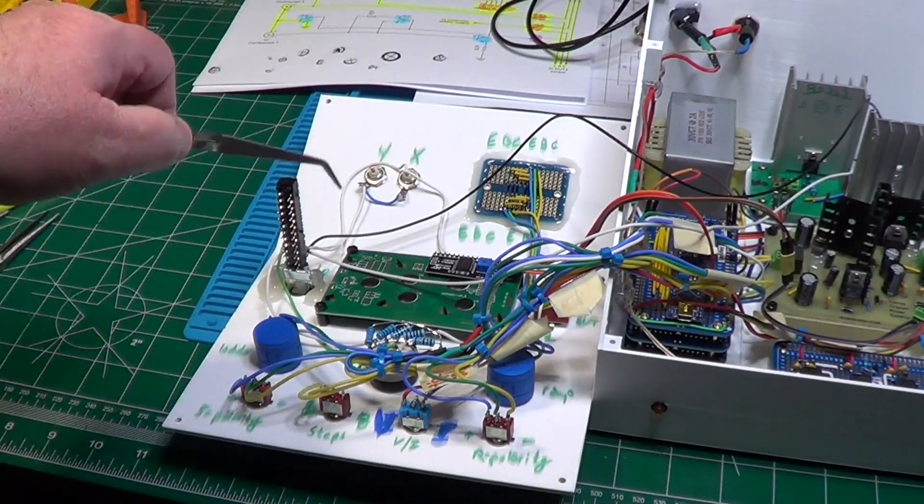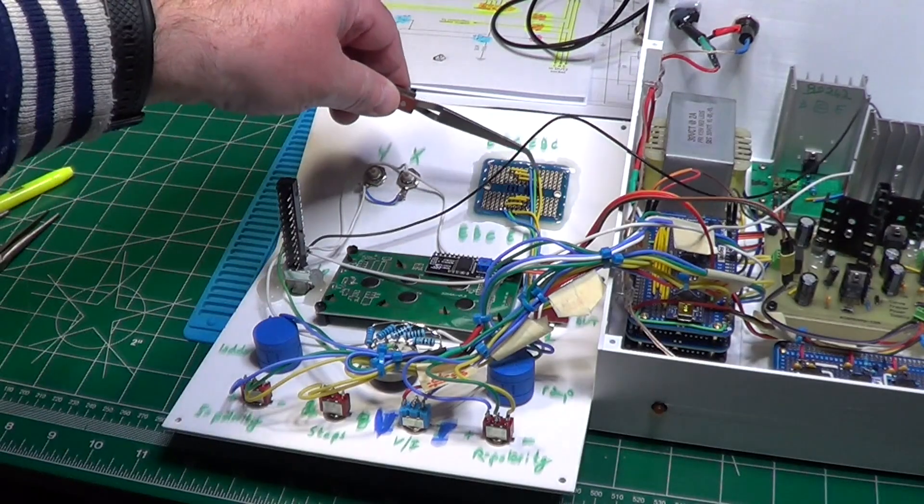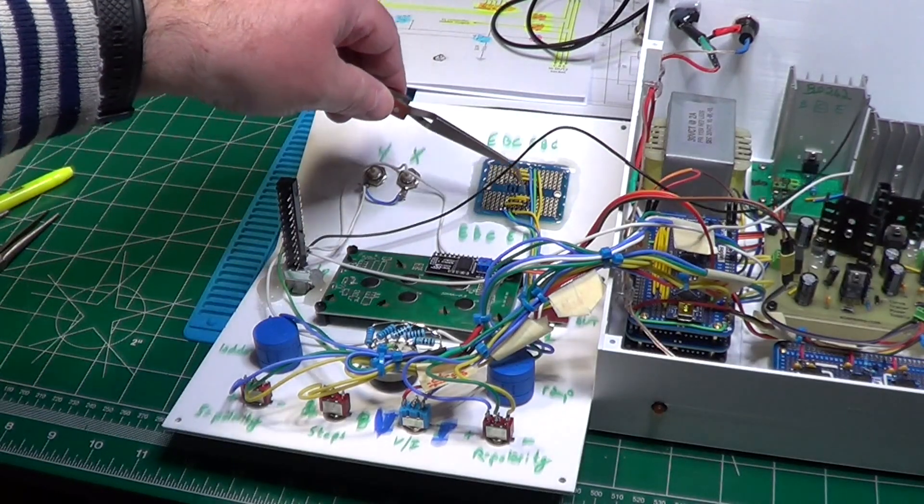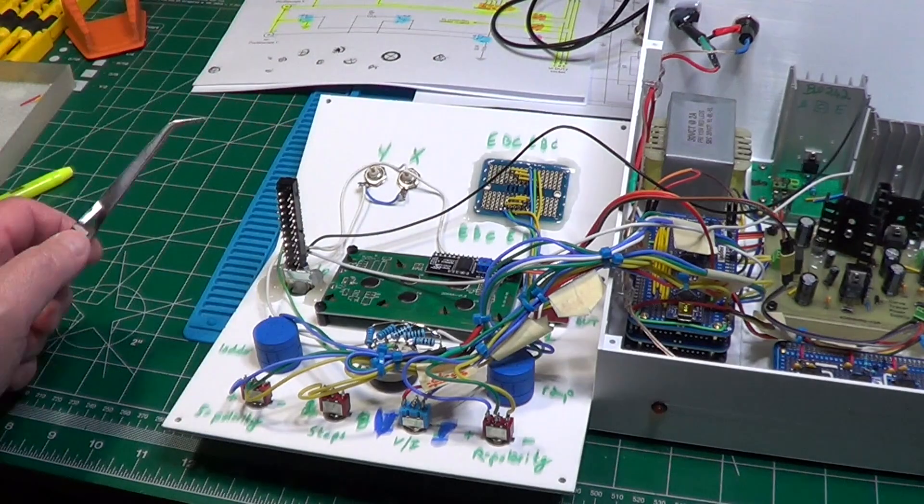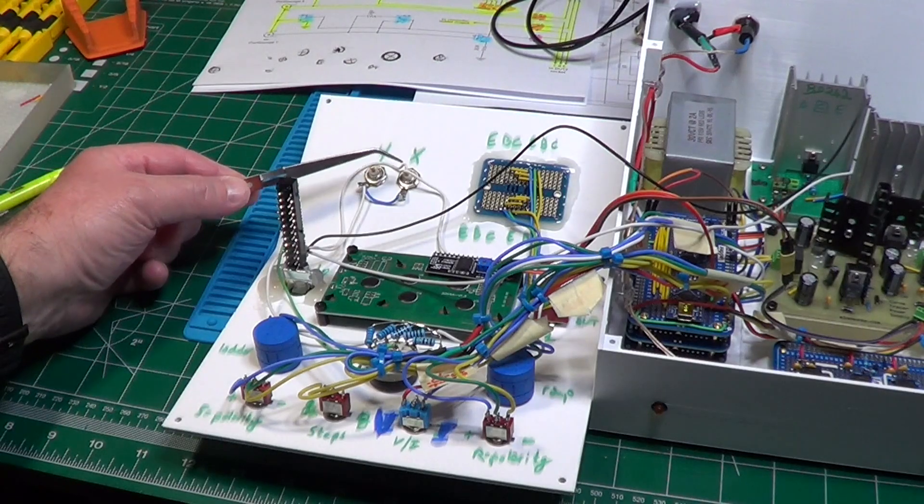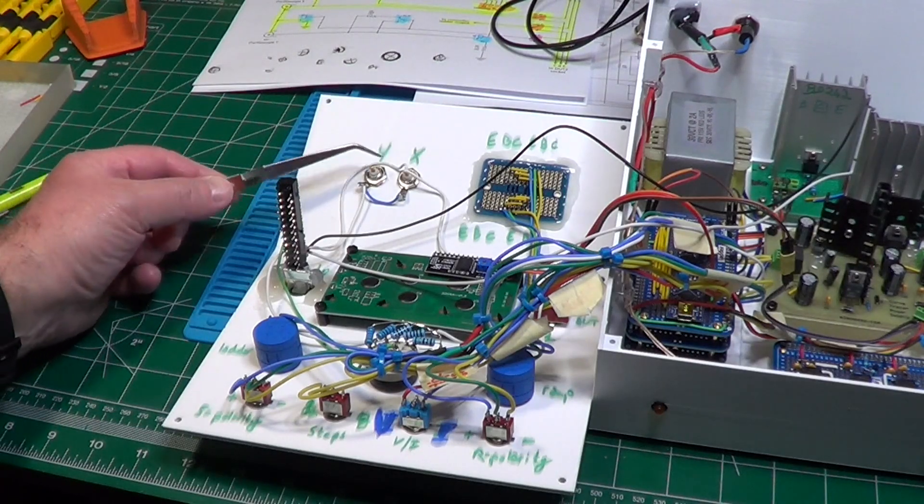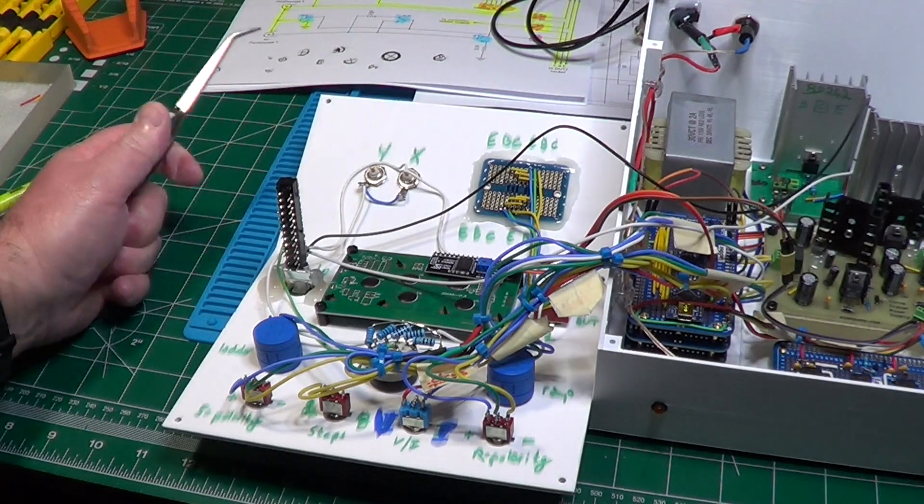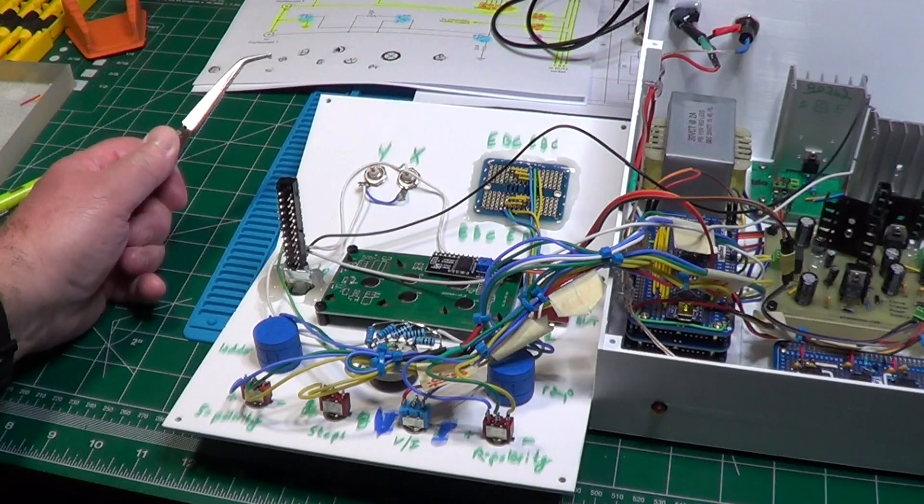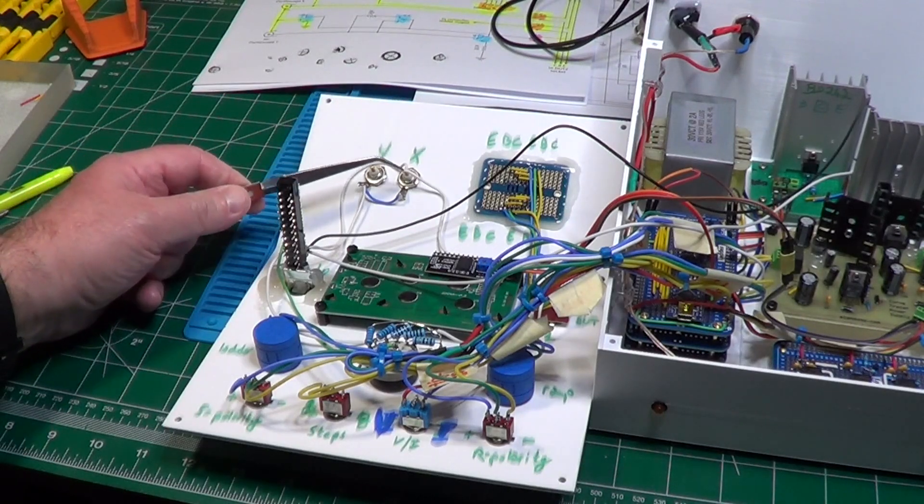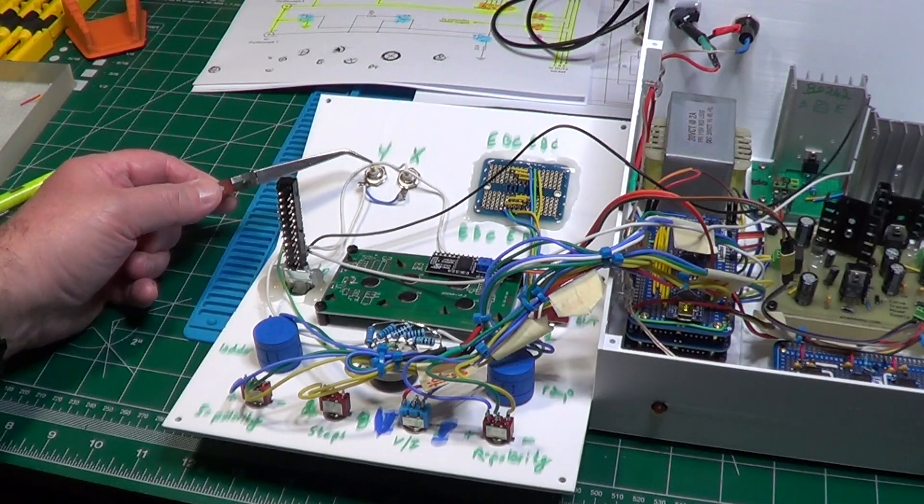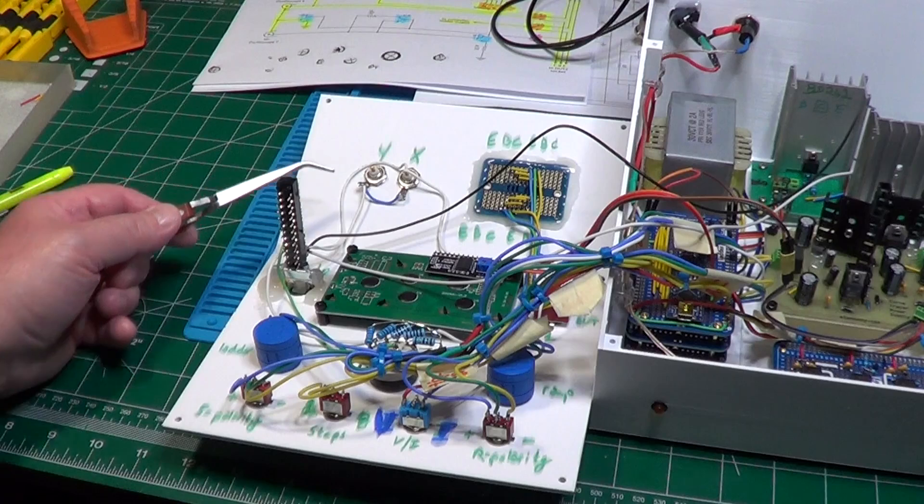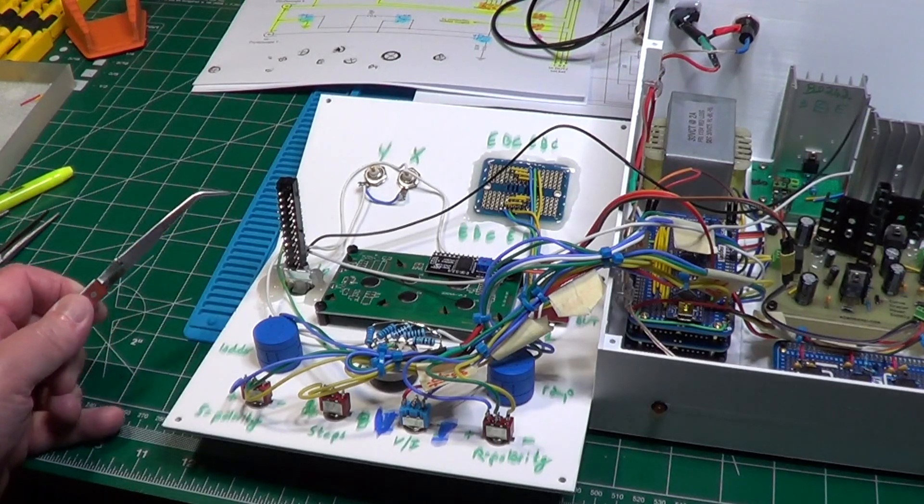Going back to the back of the front panel, these are the connections to the sockets for the DUTs. These are the BNCs for connecting the X and Y axis of the oscilloscope. The only one actually connected right now is the X axis. I will connect the Y axis wires later on.